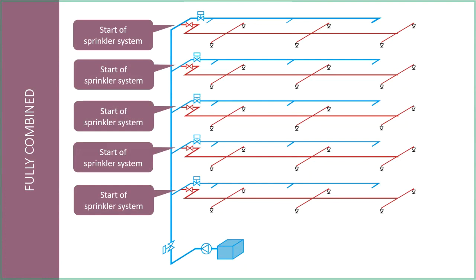And the reason I bring that up is because that was pointed out to us at Project Fire when we first released our residential zone check with a small bore drain. Our customers said, we want to use it on a combined system, and therefore we need a full bore drain. The difference is that the small drain is fine for draining the water out of the floor level, but you need a full bore drain in order to do a full flow test, which is generally done over by the pump and the tank. But in this instance, it would have to be done on each floor level. So that's something to bear in mind: the testing and maintenance schedule for a fully combined system is greater than if you have a semi-combined or standalone system.